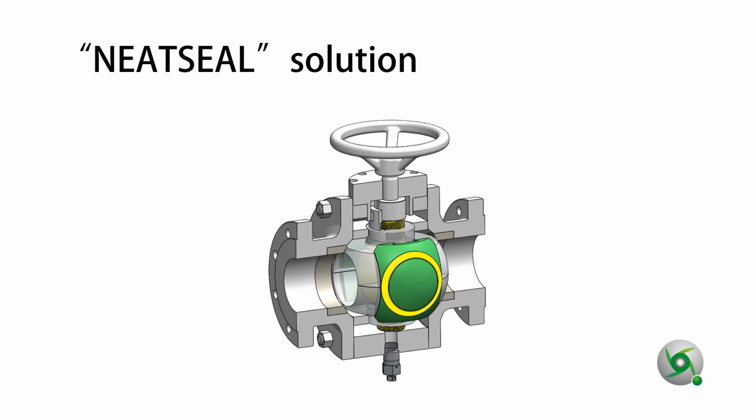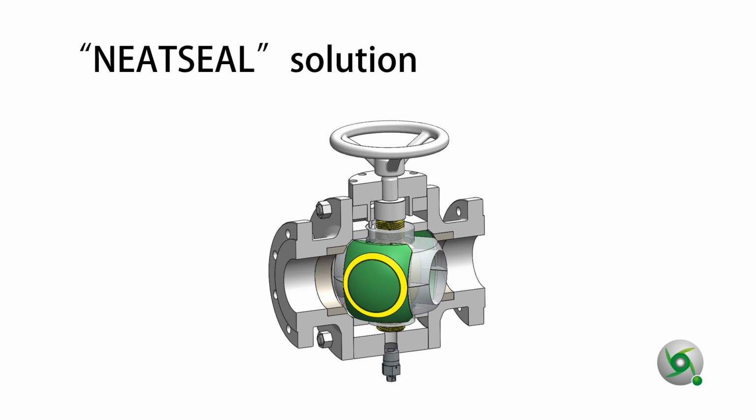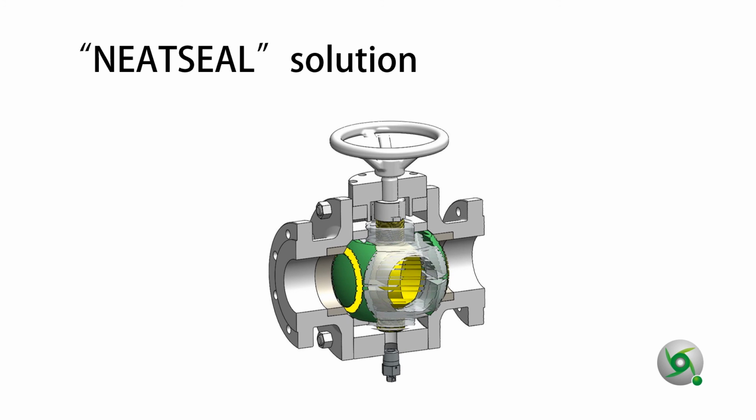Neat seal ball valve perfectly meets all requirements for metering application. It is through conduit in open position. When closing, the ball assembly will rotate to close position friction-free between seat and sealing members. Further rotating the stem will cause the sealing members to be pressed mechanically towards the seats, so two mechanically energized seals are achieved regardless of the line pressure. It meets both DBB and DIB.